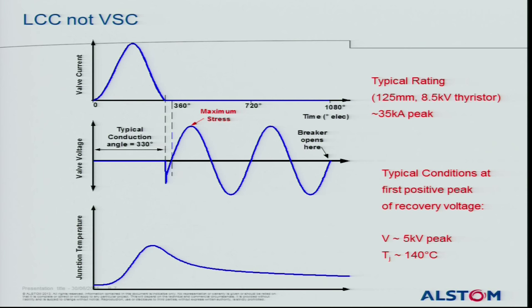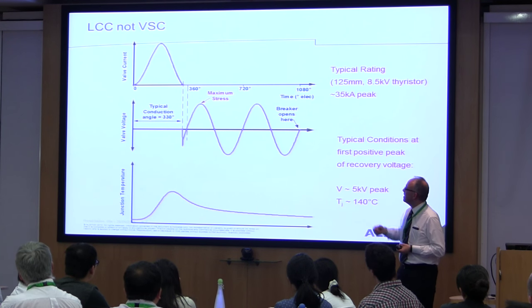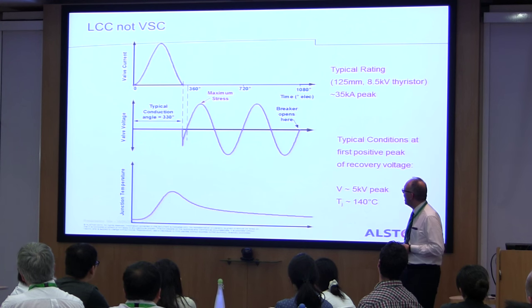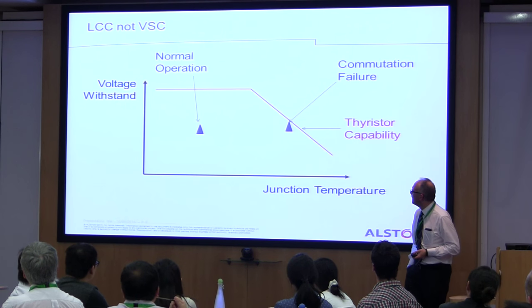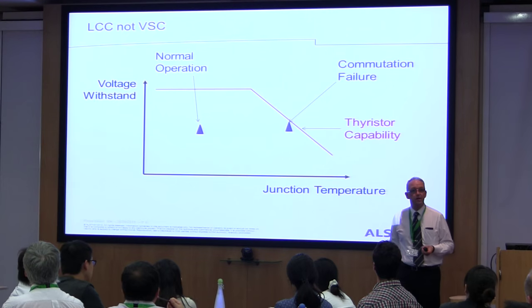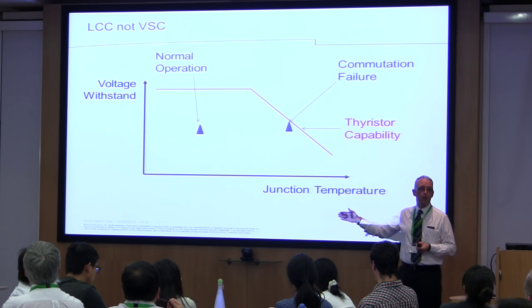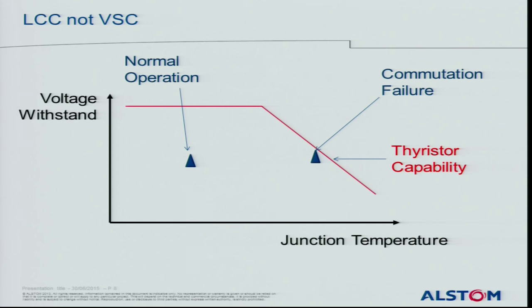From an HVDC design point of view, you can't stop commutation failures from happening. There is always the risk that a sufficient magnitude shift in the AC system will cause one. You can mitigate the risk, but you always have to design for it — taking into account the increase in junction temperature in the thyristors and the voltage they will see on recovery. So from a valve design perspective, we must account for both normal operation and transient events such as commutation failure, while remaining within the thyristor's capability envelope.